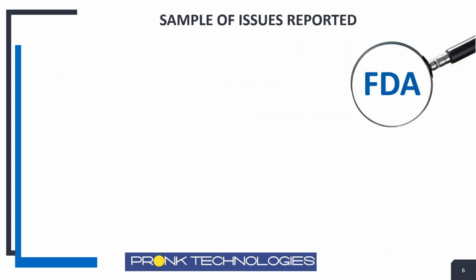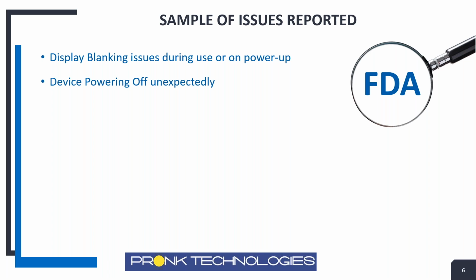So as part of the presentation, we combed that database a little bit to look for common issues that come up regarding defibrillators in general. So I looked over the last 2 years at common incidents that were reported to the FDA regarding defibs. And one of the most common ones was the display blanking. So the technician or the user is trying to power it up and the display is blanking out. The device is powering off unexpectedly. So the user's trying to use it and it just turns off. Many incidents reported regarding that.